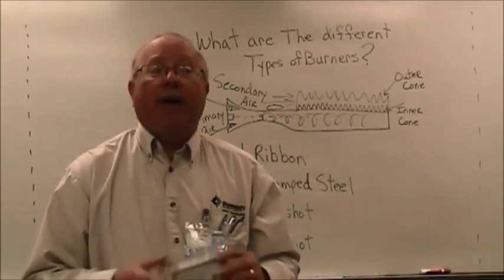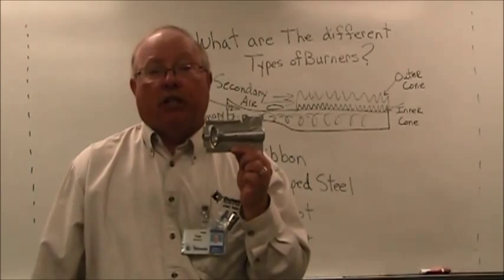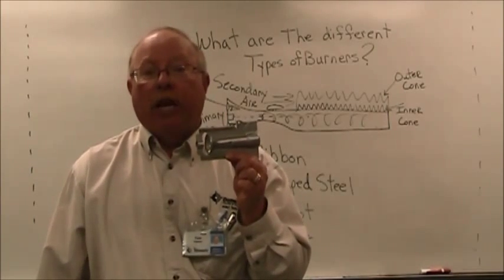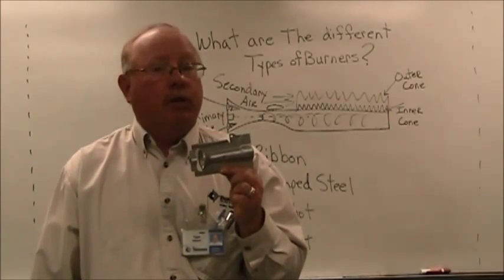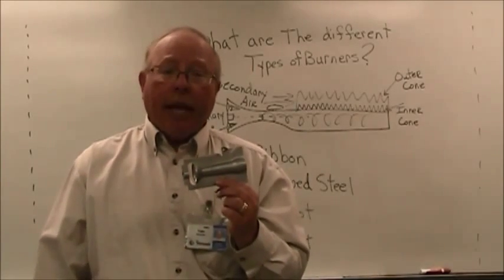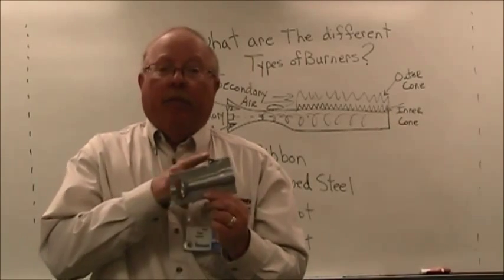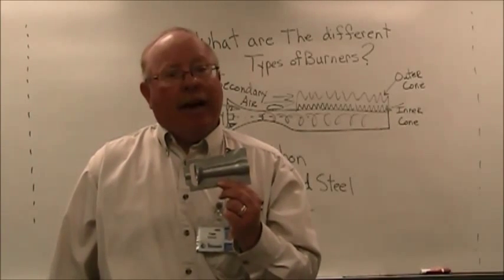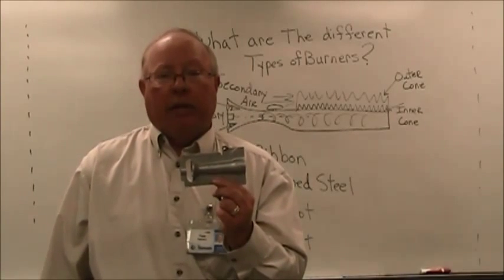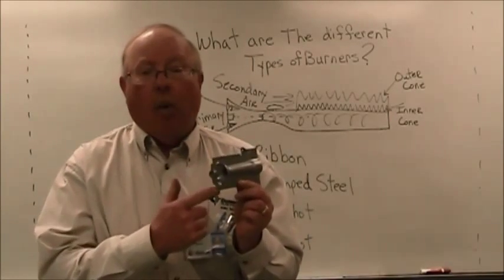Last of all, this is the most prevalent of all the burners: the in-shot burner. This burner is being used exclusively with inducer motors now. The other three can be used with inducer motors also, but as our technology has gotten better and efficiencies have gotten higher, the in-shot burner has allowed itself to become the most prevalent burner being used in our furnaces today.